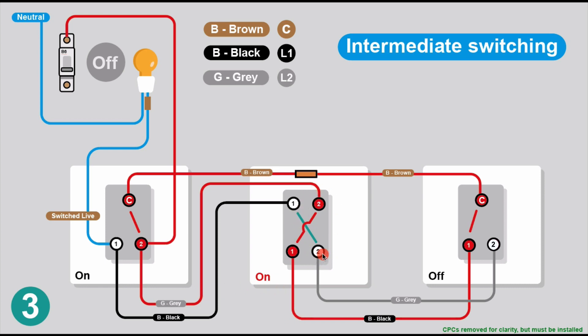Now we switch the intermediate switch on as well, with the first switch still on. Following the power both ways: going through the common it goes through the second two-way switch, through the intermediate, and just loops back to the live connection - not getting to the light. Following the grey wire the other way, it goes through the switch and crosses over, creating another loop. We're not getting to this connection. So the light is off.